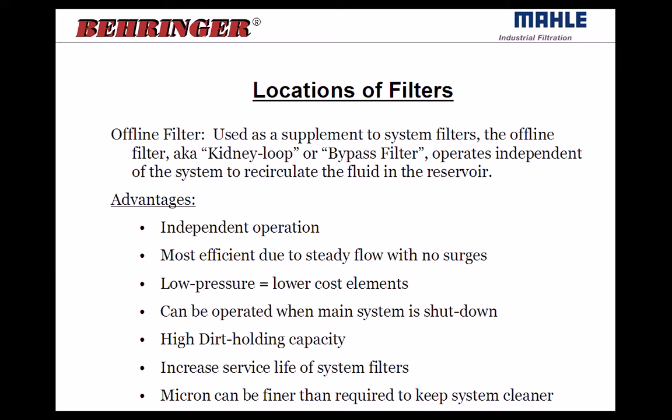Typically, you want to have a large filter with large dirt holding capacity, so you don't need to change the element as frequently. By keeping the oil in the reservoir clean by using a kidney loop or an offline filter, you increase the service life of your system elements, your high pressure filters, which are more expensive. It's also recommended to have a finer micron rating on an offline filter than what's required by the system. So if you have a servo valve or proportional valve system that requires 10 micron filters, you can put a 3-micron or 2-micron filter in the kidney loop.